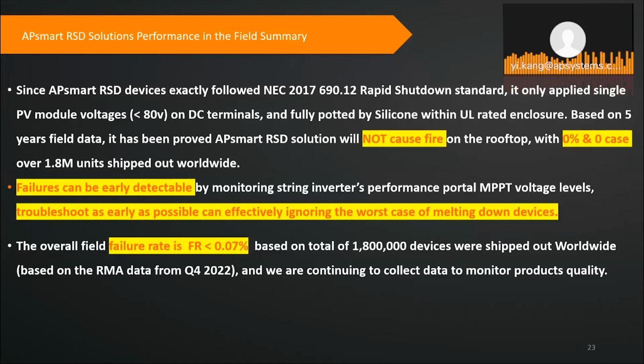For comparison, if you're talking about optimizers, some of those companies are claiming something like 0.75% annual failure rate on an optimizer, or maybe 1%, right? So much higher than a rapid shutdown device like this, which has a very low failure rate. That data is from last year, 2022. When did you start selling these? 2019. Okay, so three years. So yeah, that's really impressive. Thank you.